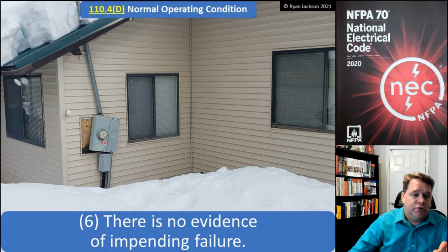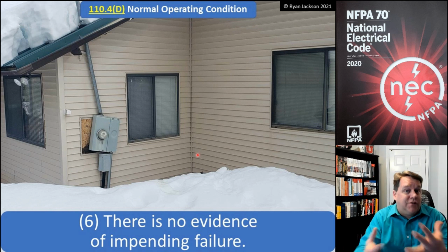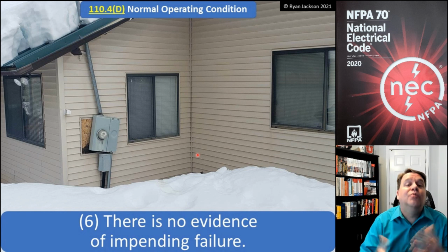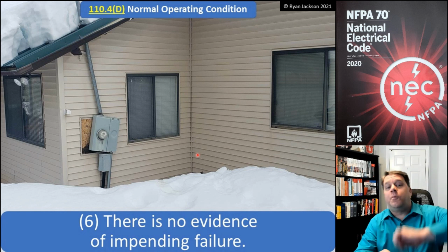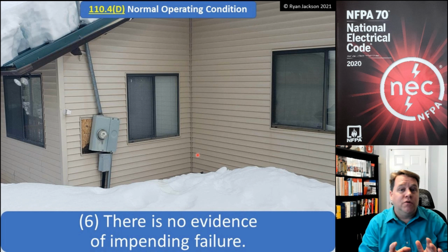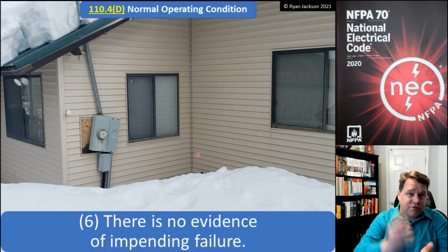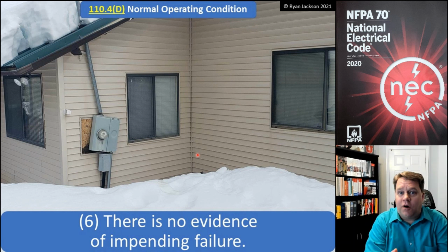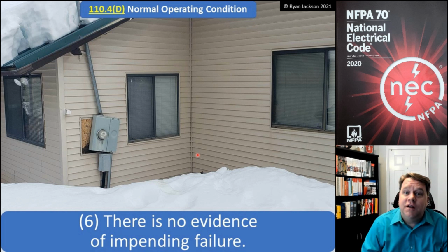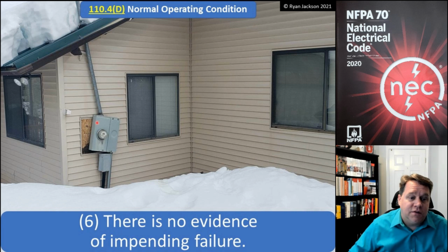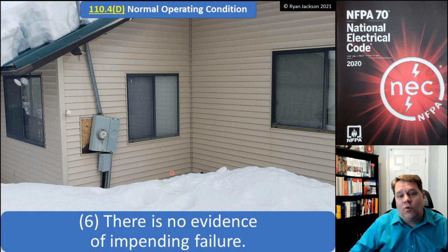Where are those screws or screw heads, best case scenario, that used to hold this thing to the wall? They're kicking around somewhere inside of that equipment. Who knows where they are? Just opening that door might move it enough to drop one of those screw heads up against the energized parts, and we could end up having an incident. So no, there is no normal operation of this equipment because that's not in a normal operating condition. There's evidence of impending failure.